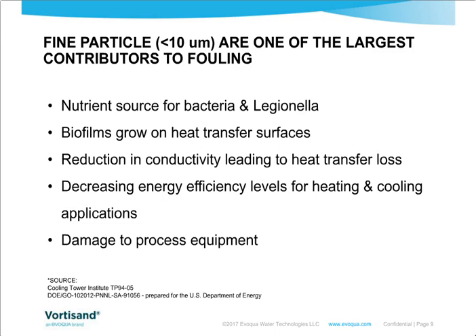Now, why are these fine particles of such interest? Fine particles less than 10 microns are one of the largest contributors to fouling. This is a very important part of knowing what type of filtration technology you need. Those fine particles less than 10 microns are the major source of solids and nutrients for bacteria such as Legionella and other microorganisms. As those particles keep feeding that bacteria, you're going to start developing biofilms. These biofilms can accumulate over time on heat transfer surfaces, your chiller tubes, your heat exchanger surfaces, etc. And over time, those biofilms will reduce the conductivity of those heat transfer surfaces, leading to heat transfer loss.